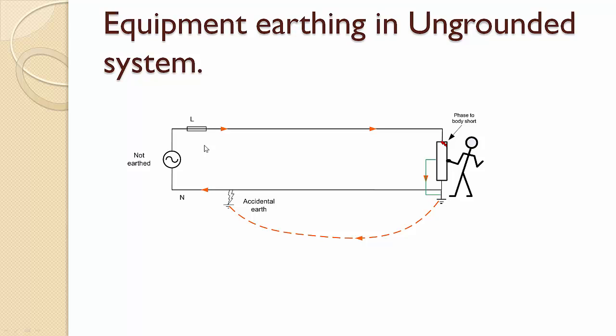This may prevent the fuse from blowing and thus isolating the fault and alerting us to the presence of a fault or the presence of a ground. So it is better to establish a clean, low-impedance path for the earth fault current through the body of electrical equipment in the first place itself to cater to any potential electric shock.